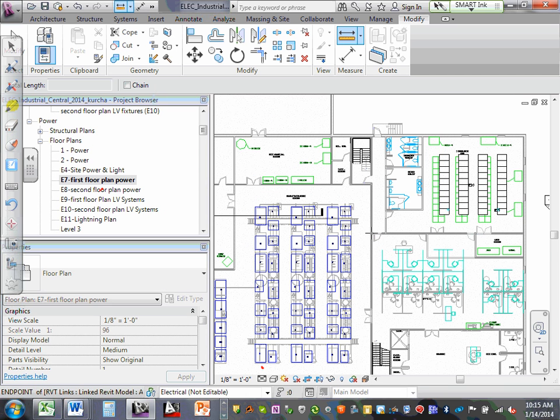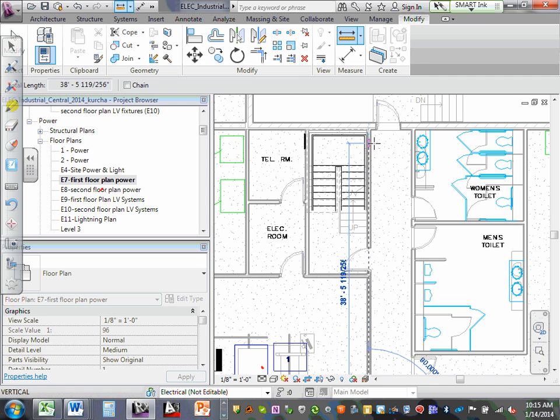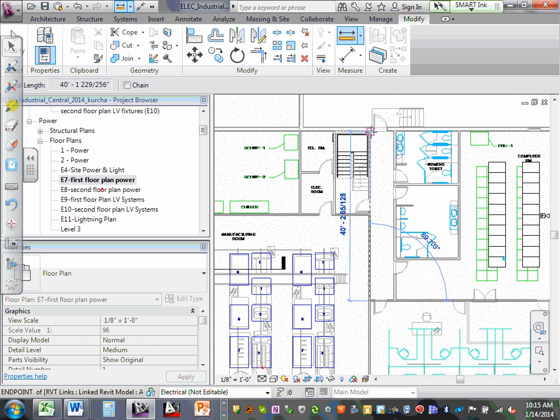The only rule that really applies is that in corridors, you must be within 15 feet of each end of the corridor, and then you space your devices beyond that, depending on the length of the corridor. So 40 feet, you're going to have to have two devices in that corridor because you've got to be within 15 feet of either end. Okay.